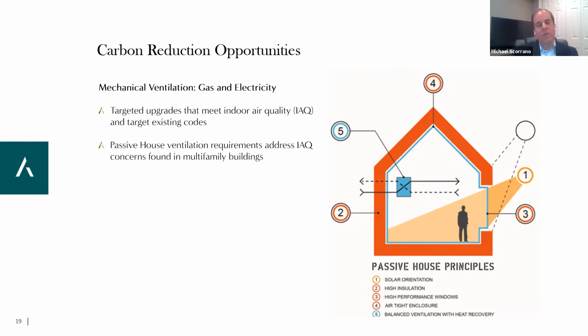So what we find we can do is a couple of things. First, look at the building and figure out what it was originally designed for, and where we can reduce it based on new standards and passive house ventilation standards. We can reduce the amount of exhaust air pulled out of the building, and also balance the lines over time. By focusing on each line individually, we reduce the air pulled out, which reduces the air pulled in, which reduces the energy needed to heat and cool that air - a big energy efficiency piece.